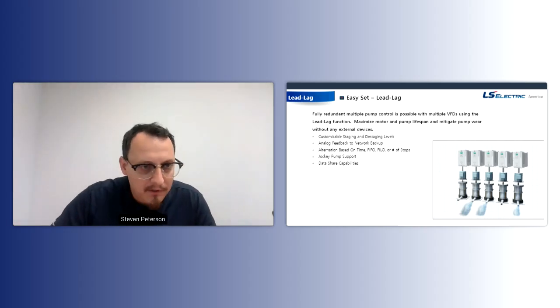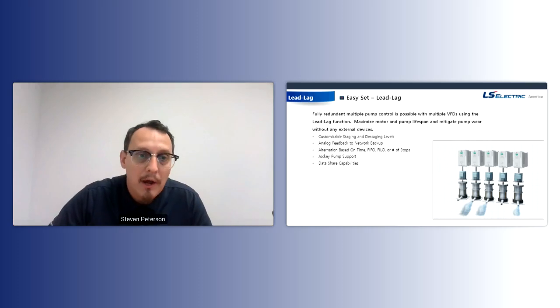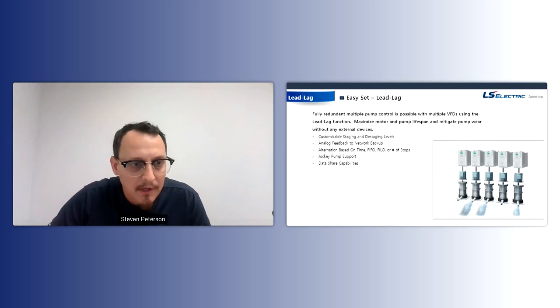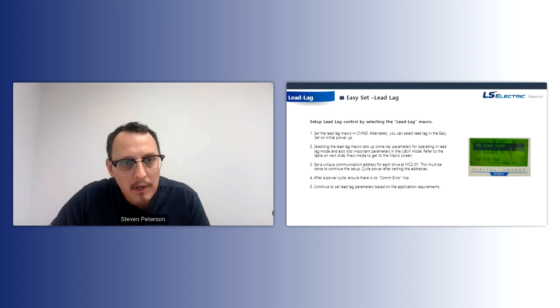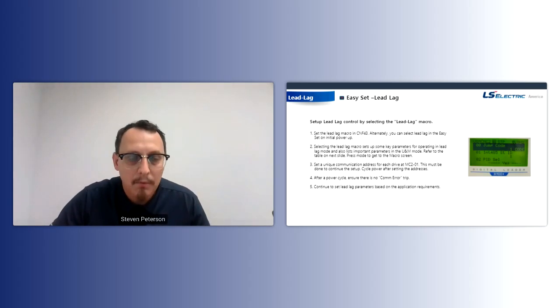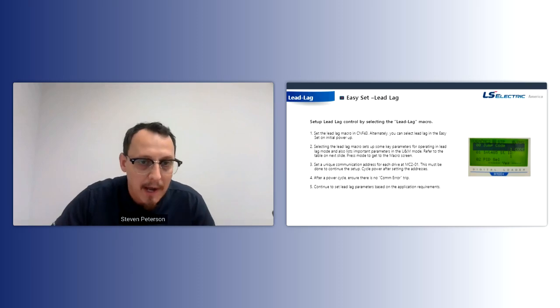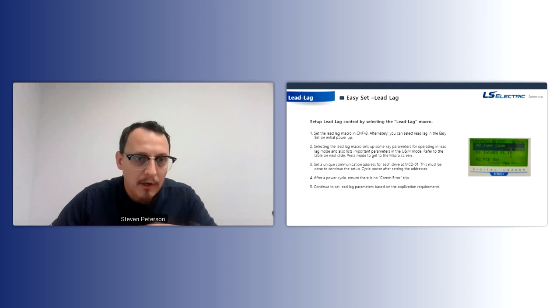Okay. So next thing I'm going to do here is show you how you would set up a lead lag setup. So lead lag setup, as I mentioned, is just selecting the macro. First thing you see, basic pressure control lead lag. This is the third option. So you select lead lag. Also, if you don't select it on that first startup screen, you could always go into the configuration on the drive and you can manually select your macro.